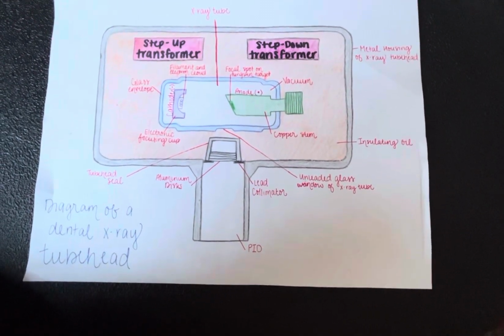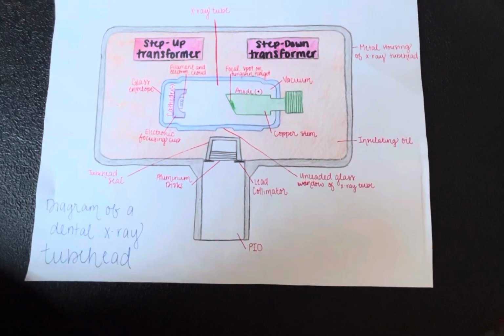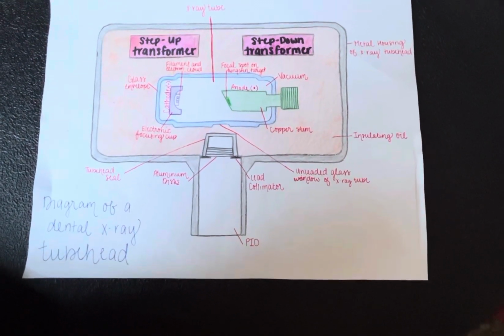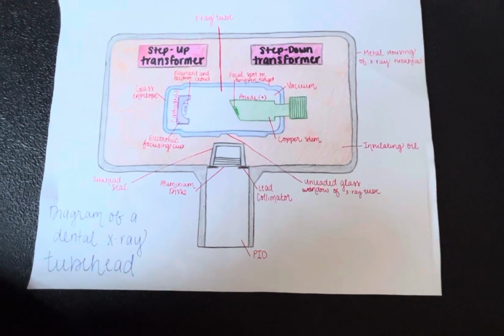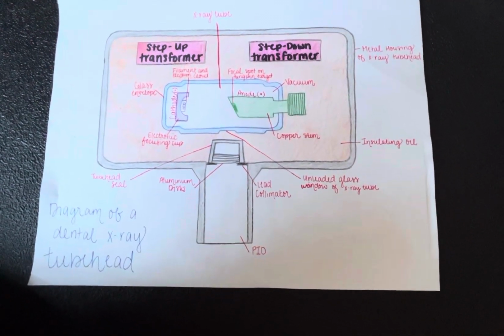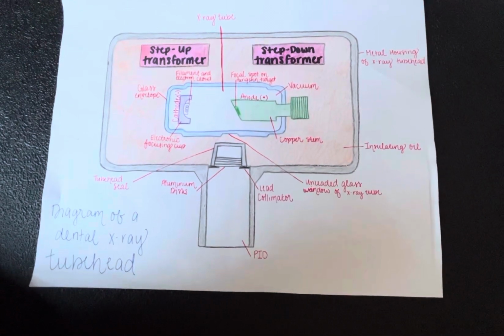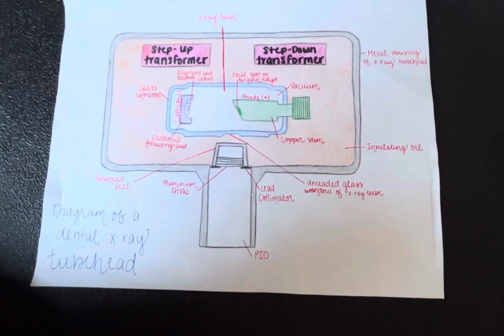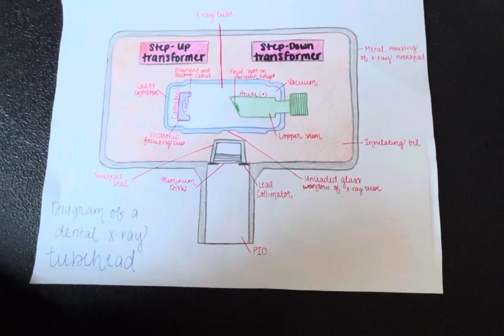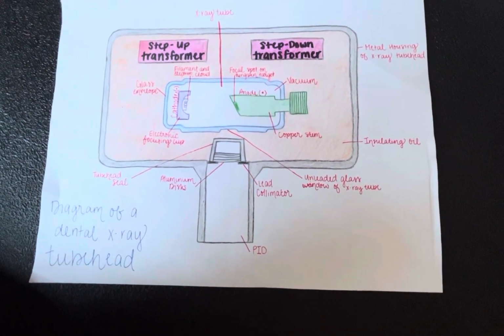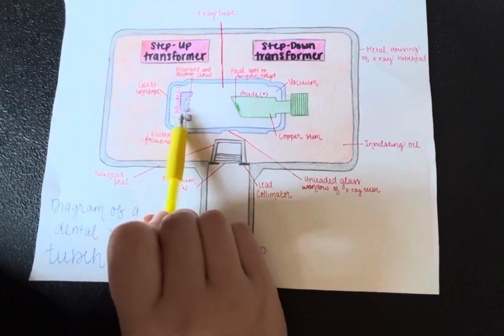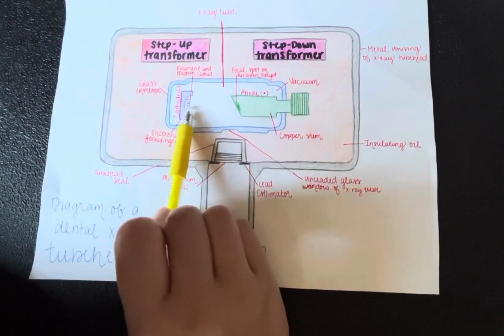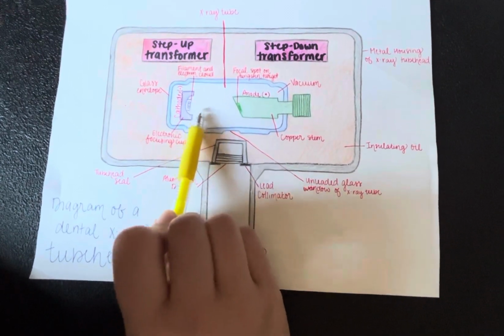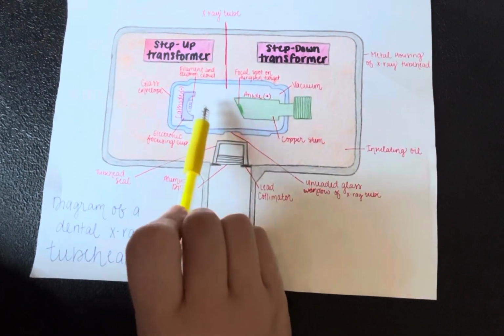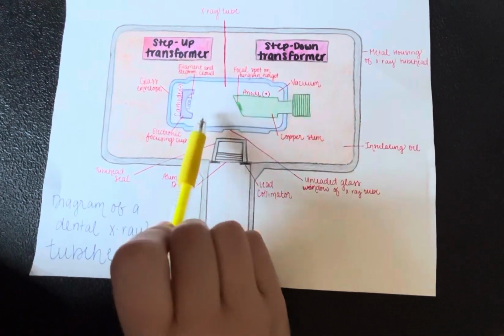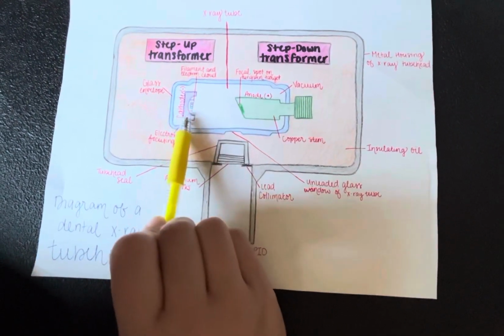So now that we have all the details of the tube head and the components of the X-ray production, let's go over a step-by-step explanation of how X-rays are produced. First, when the machine is turned on, the electrical current enters the control panel through the wall power source. The current travels from the wall to the control panel to the tube head through the extension arm. The current is directed to the filament circuit and step-down transformer in the tube head. The transformer does its job by reducing the incoming voltage to 3 to 5 volts. The filament circuit uses 3 to 5 volts to heat the tungsten filament on the cathode of the X-ray tube.